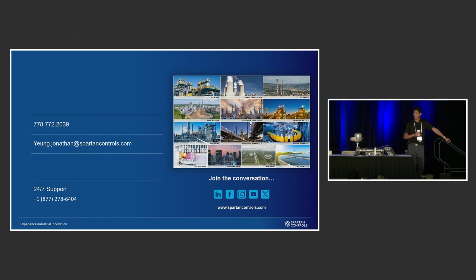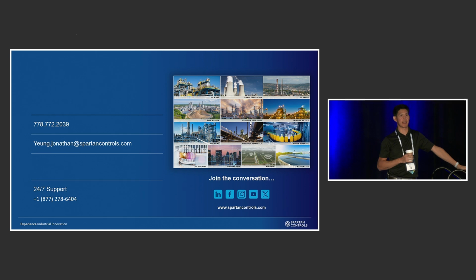Great question. On most applications they're the same. The only time we'd go to a single path is if it affects the amount of time we need to get the transducer from one side to the other. What I mean is, say we have a very light liquid or a gas — typically a single path across will be a very short duration and we won't have the resolution to go directly across. If we have something heavier, like water with some solids in it, we could mount that and really tighten up how much space we need to install one of these units.